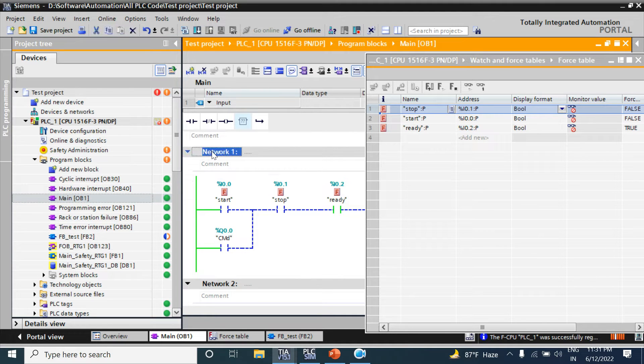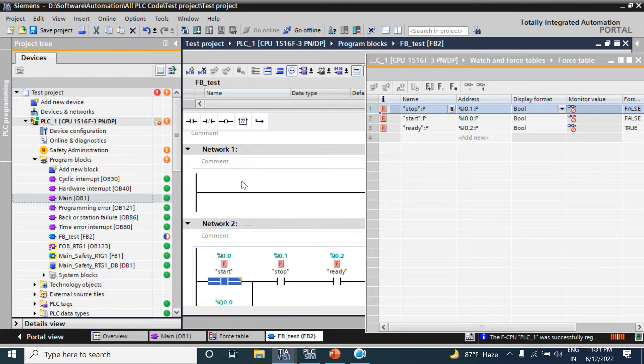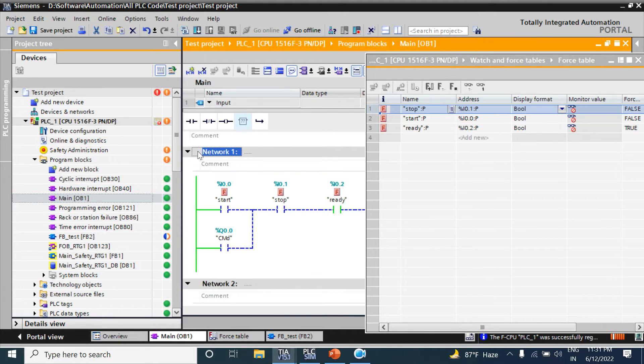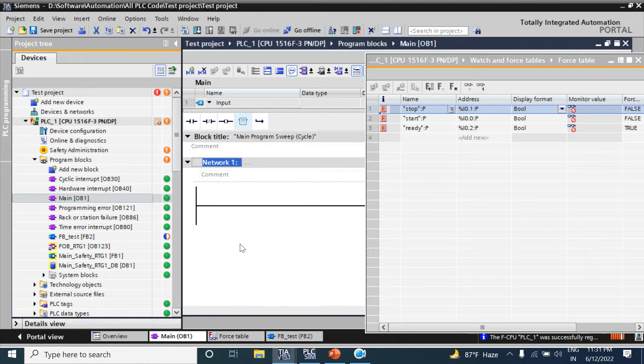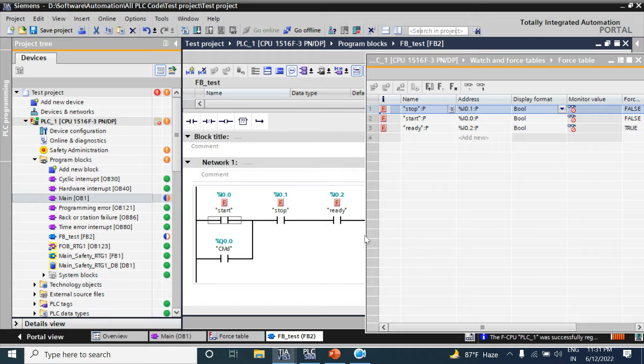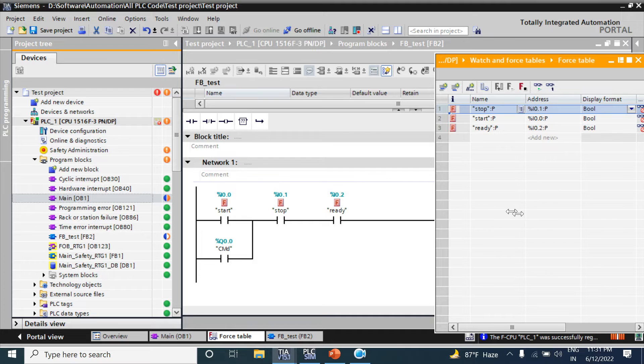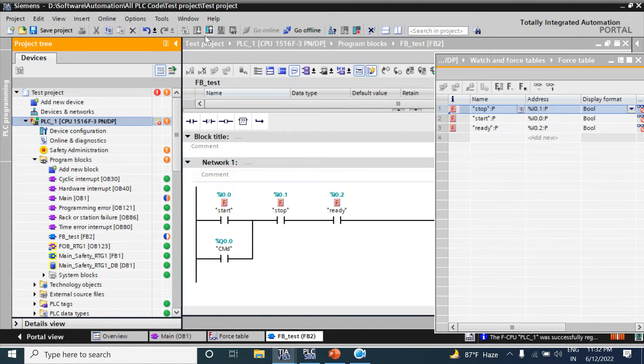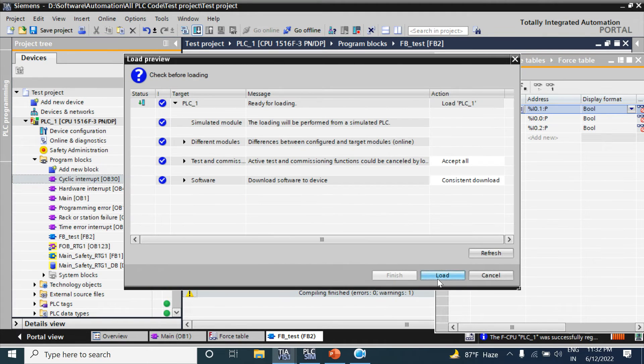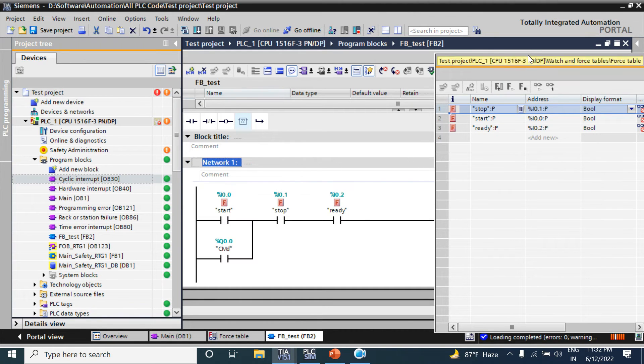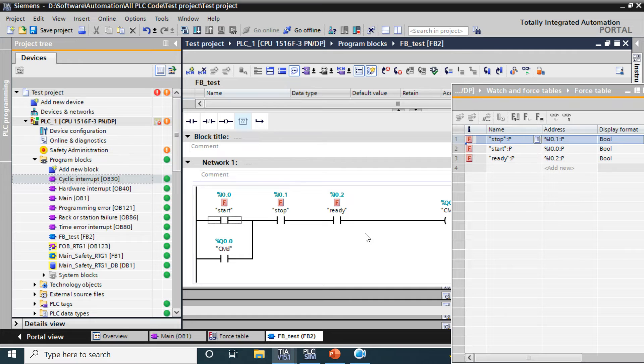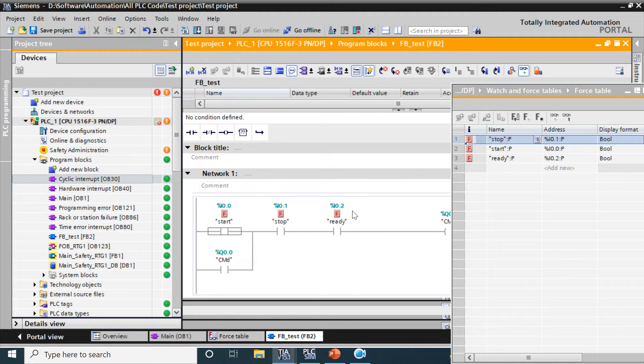I just copy and paste the program into the new FB. I delete the original from OB1 because we don't need it written in both places. Now I go to download this program. I can see it is not executing because I have not yet called the FB Test block in OB1.